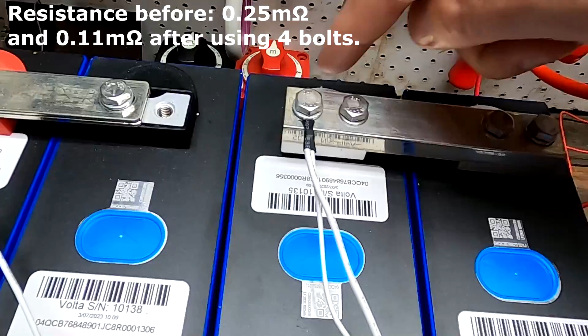Well, anyway, it is now 0.11 milliohms, same as all the other ones. It was 0.25 milliohms before, and hence we had a higher voltage drop on these connections and therefore more heat creation as well. So this is now all fixed, hopefully, and now we can start test number 3, which will be our final test, hopefully.